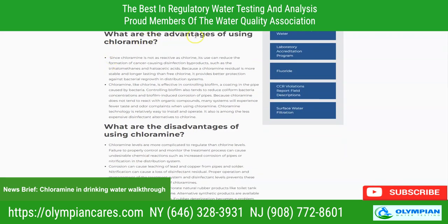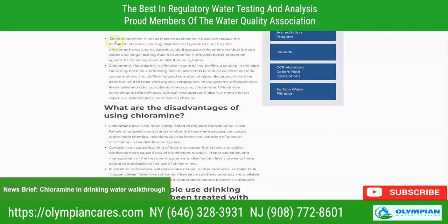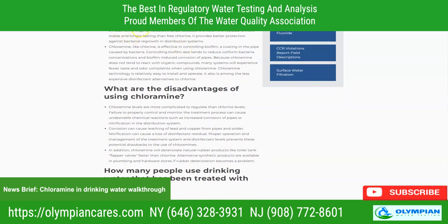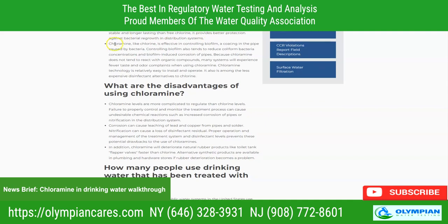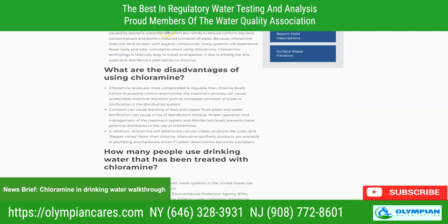What are the advantages of using chloramine? Since chloramine is not as reactive as chlorine, it can reduce the formation of cancer-causing disinfection byproducts such as trihalomethanes, THMs, and haloacetic acids. Because chloramine residual is more stable and longer lasting than free chlorine, it provides better protection. Also, chloramine, like chlorine, is effective in controlling biofilm, a coating in pipes caused by bacteria. Controlling biofilm also tends to reduce coliform bacteria concentrations and biofilm-induced corrosion of pipes, and because chloramine does not tend to react with organic compounds, many systems will experience fewer taste and odor complaints.